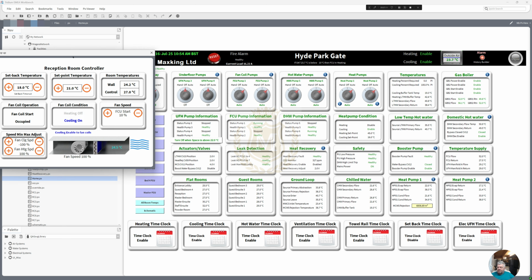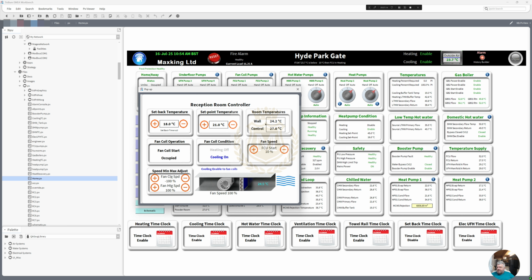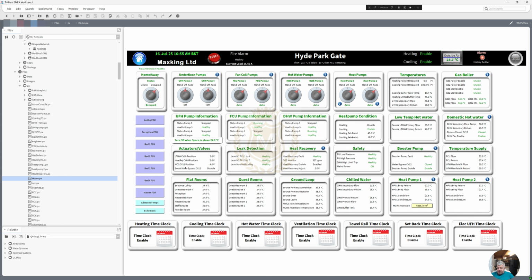Again, this one's just gone across to that side. So the wall temperature is 24.2, and we're supplying only 24 point something, so we're not stripping much off there. That control temperature of 27, that's on the room thermostat, which is located normally near a light switch or near a door. So you can't really take that into consideration for a thermistor that's built into the remote control unit for the fan coil. This is a better temperature to take into control, the 24.2, not that 27 degrees. But that's basically the wall controller giving 27 degrees, but the temperature sensor inside the room is giving 24.2. So that's the sensor that we would be using.